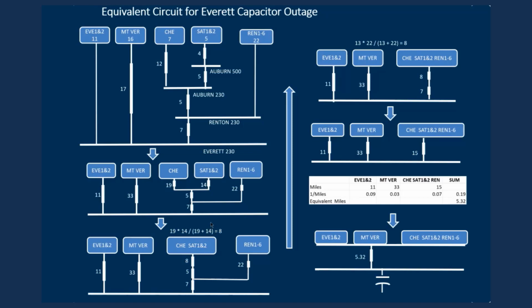The next step is to do a parallel combination. We have Chehalis and Satsop both feeding the Auburn 230 kV bus in parallel. So we do our parallel combination. We multiply the reactance of path 1 times path 2, the 19 times the 14, and we divide it by the summation of the reactances, and we get an equivalent path length of 8. So we put the 8 in here to represent the combination of the 2 paths from Chehalis to Auburn 230 and Satsop to Auburn 230.